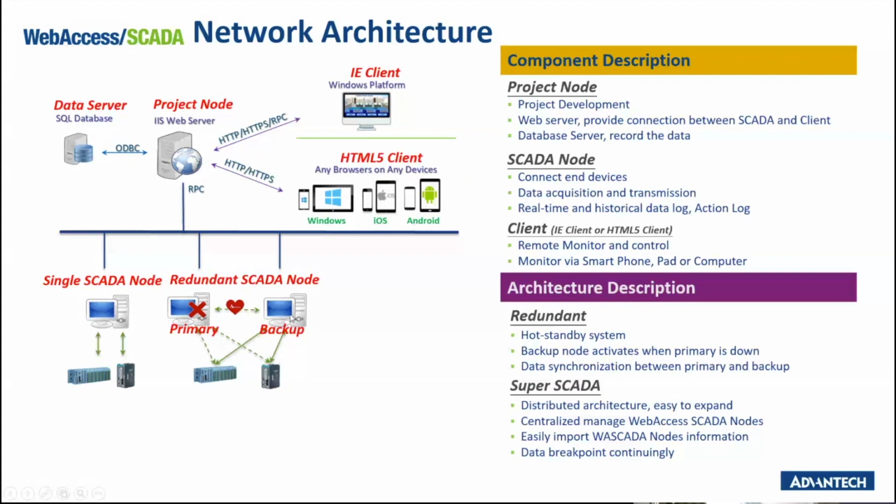These setups require a dual gateway output from the controller device towards the primary and backup SCADA node system. Switching over between the primary and backup normally takes roughly about 8 seconds upon the detection of hardware failure.